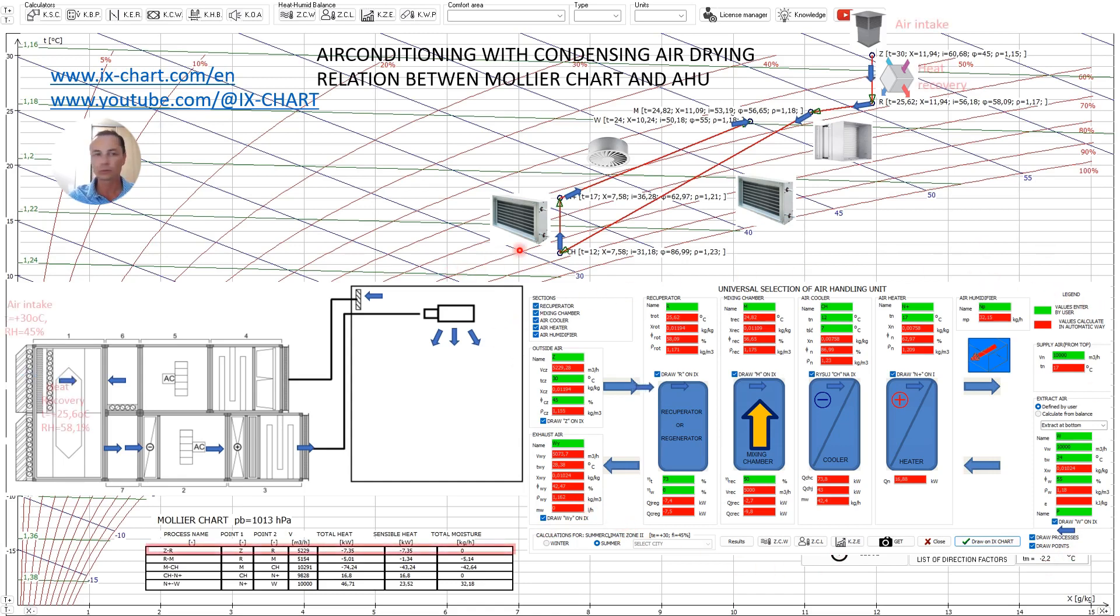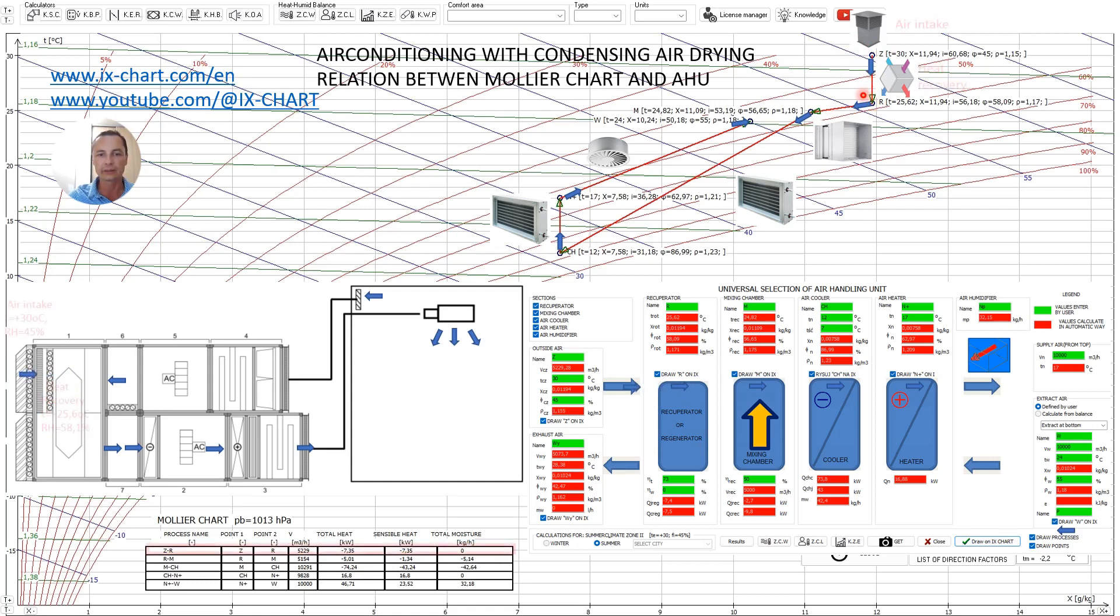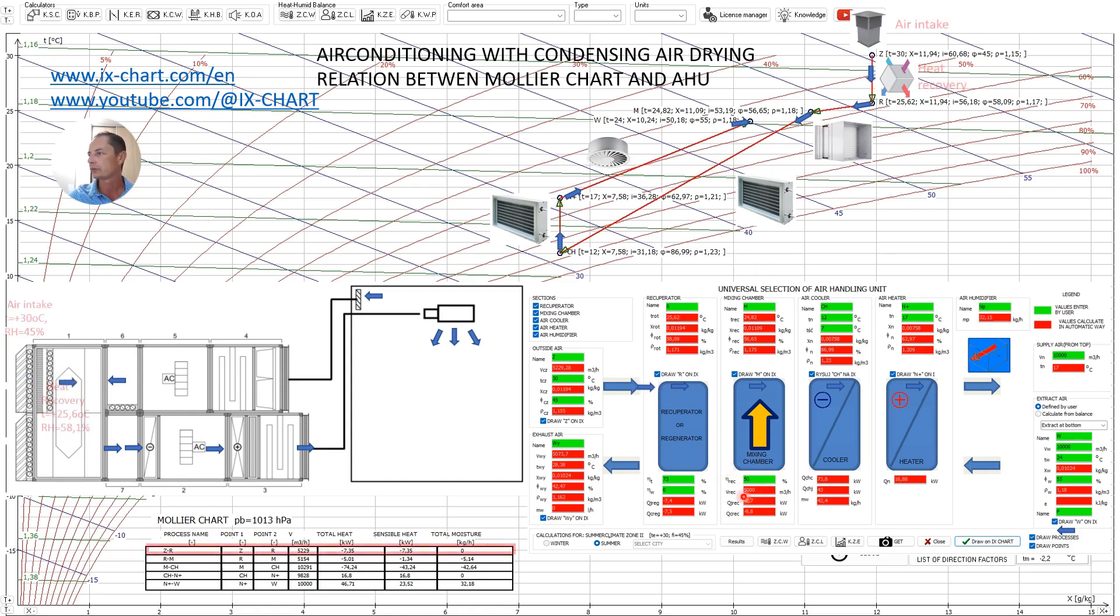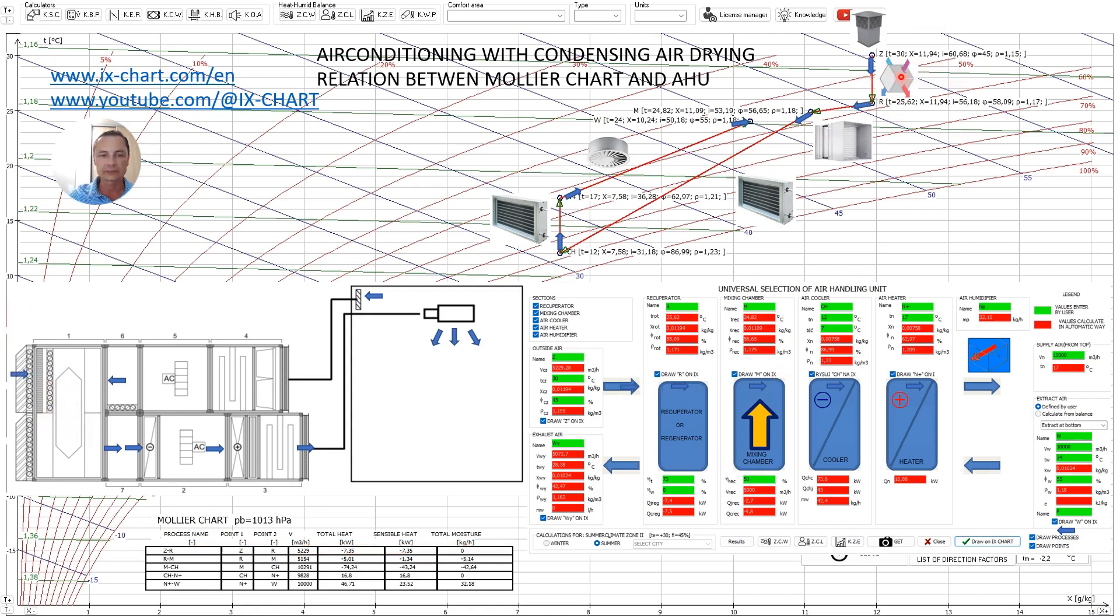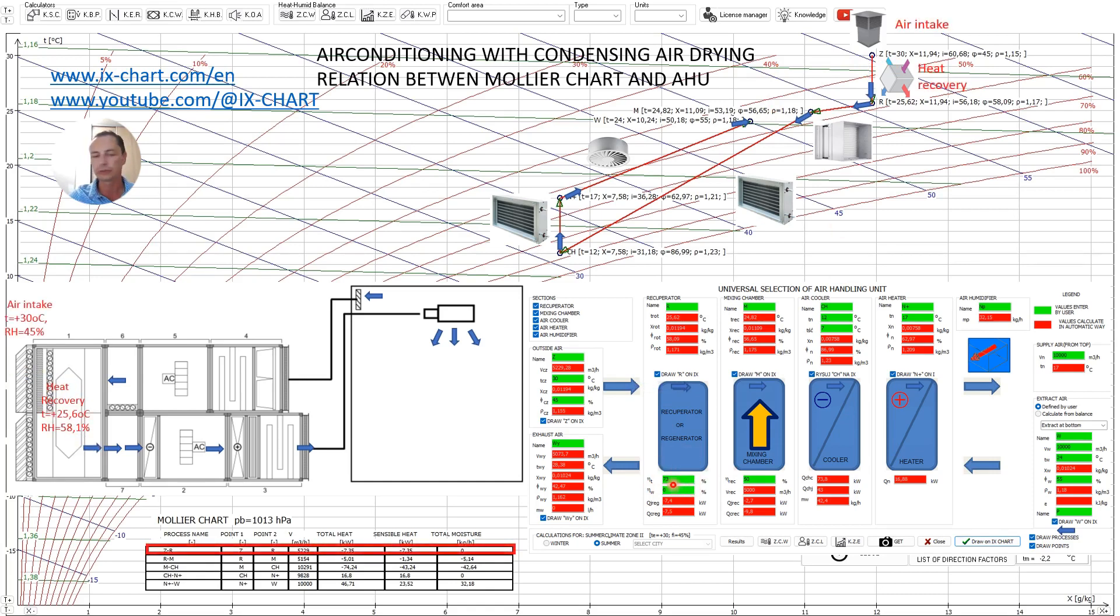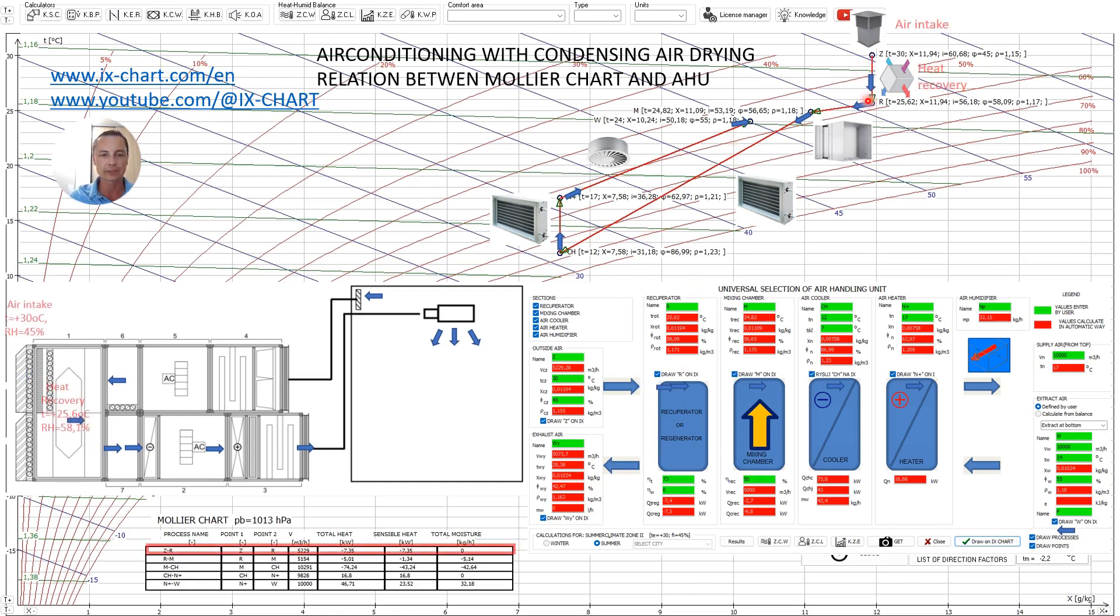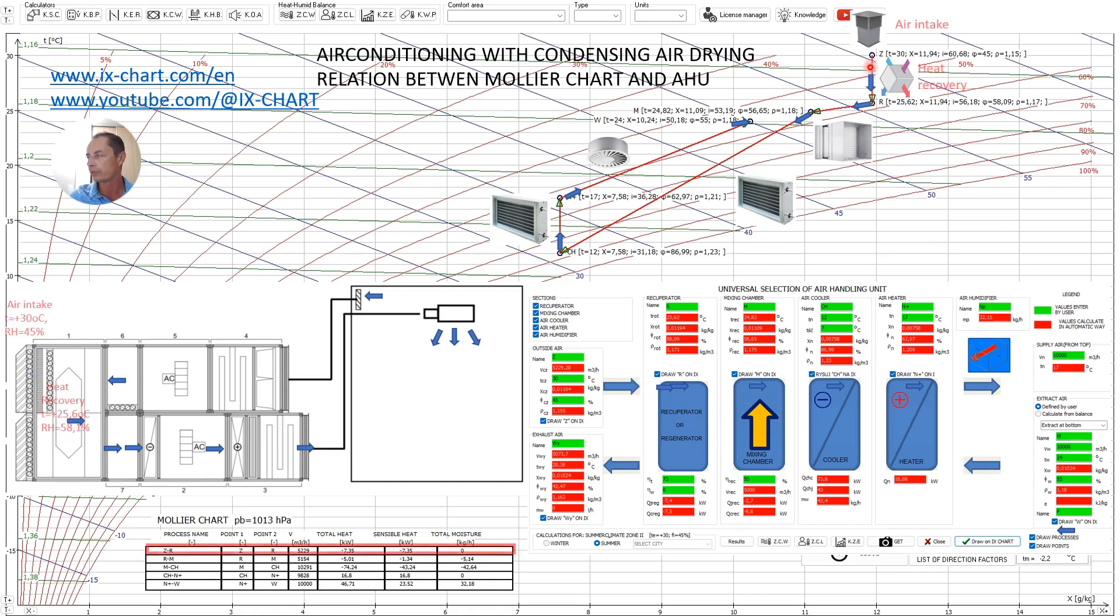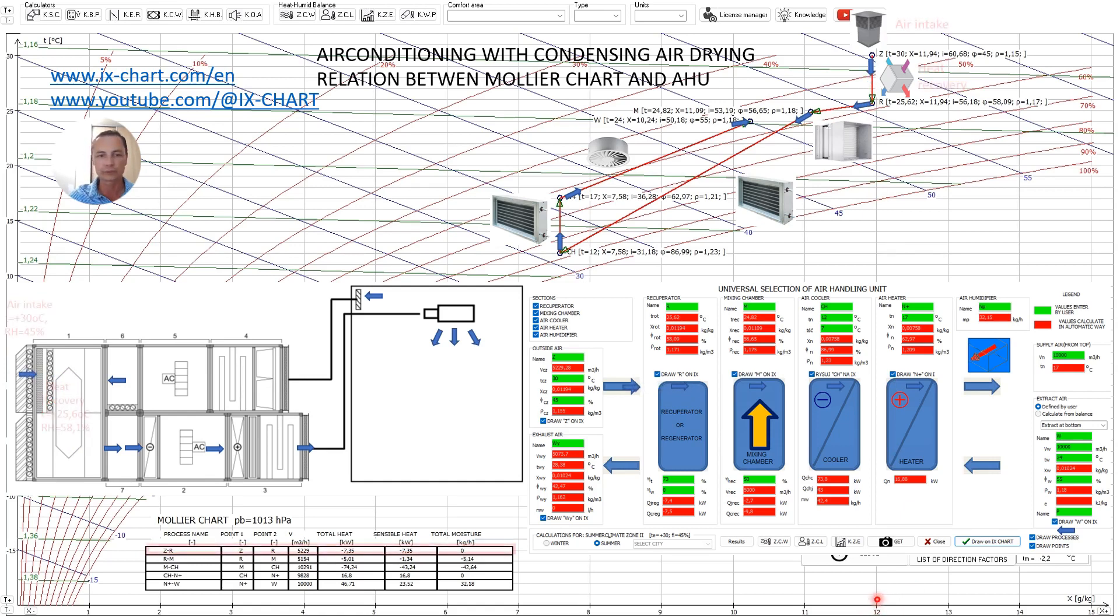So in the first step from point Z to point R the fresh air is taken by air intake in an amount equal to the mixing ratio in this case 15%. The air flows through the heat recovery section where in the summer season it recovers heat in the form of cooling of course. In this case I assumed a recovery efficiency of heat recovery section at level 73%. The process is vertical because it involves only sensible heat exchange without moisture. We have here a constant value of the moisture 12 gram per kilogram.